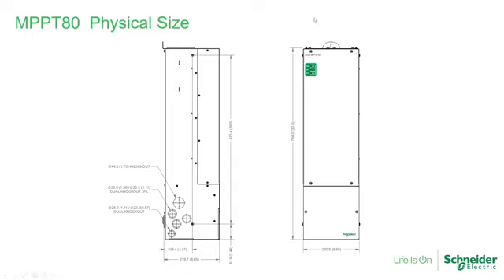The unit is NEMA 1, which means it has to be installed indoors, protected. It also has a requirement of a vertical installation. So what you're seeing on my screen is actually the only way that this unit can be installed. Okay, so you're going to find knockouts on either side. They're exactly the same. So these knockouts vary in size. For the conductors, you have the same exact knockouts on the other side, and you also have them on the back of the unit. Okay, so you'll find knockouts on the sides and on the back.